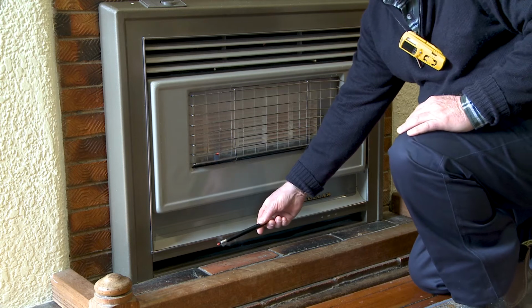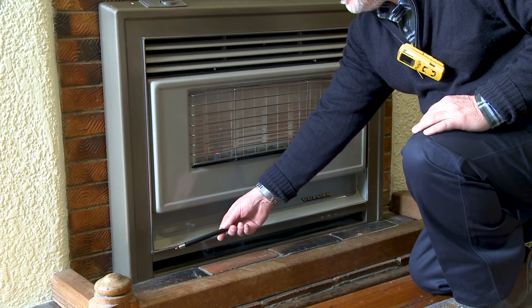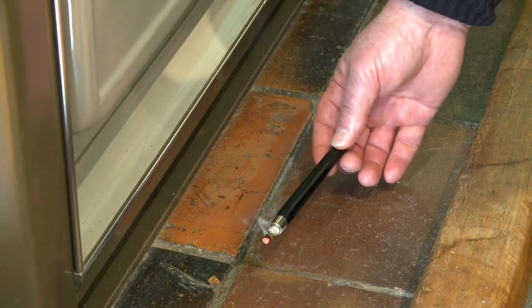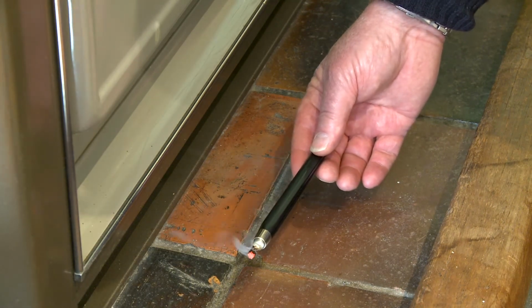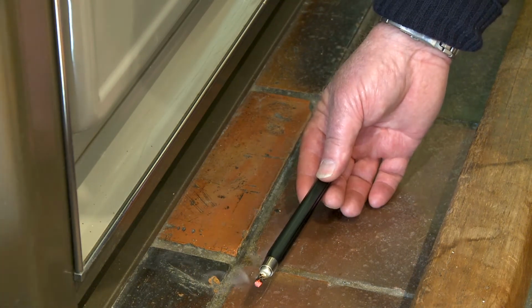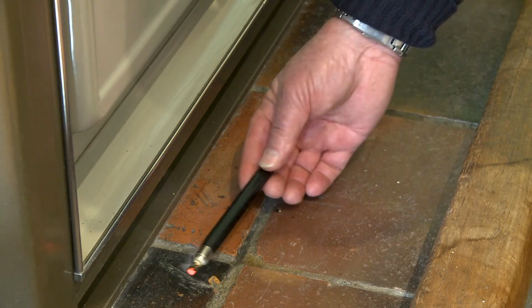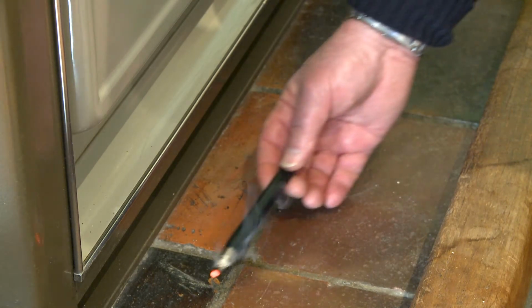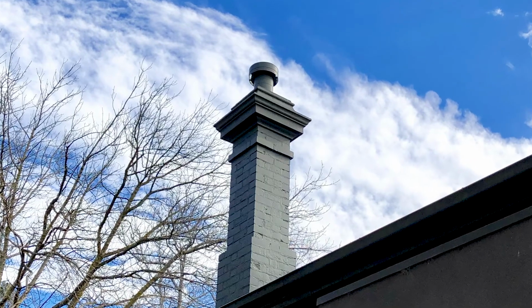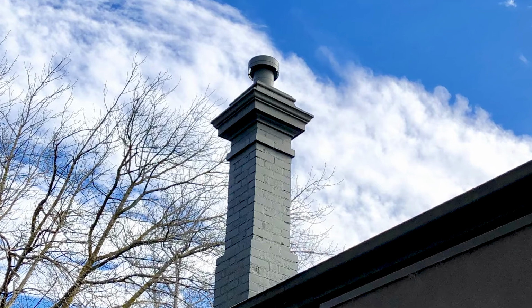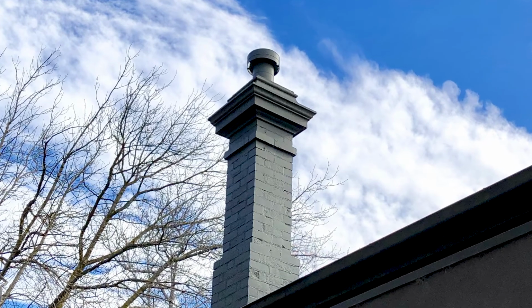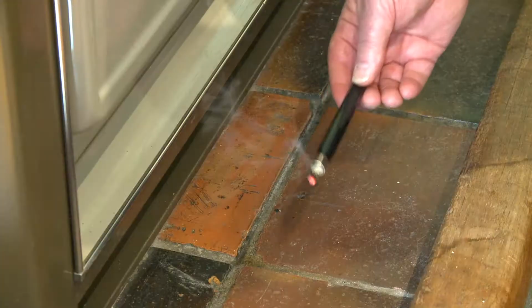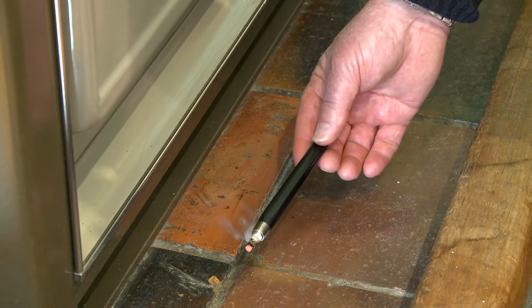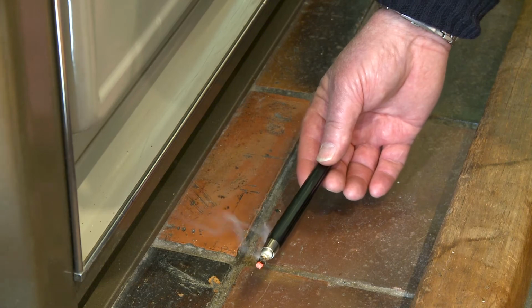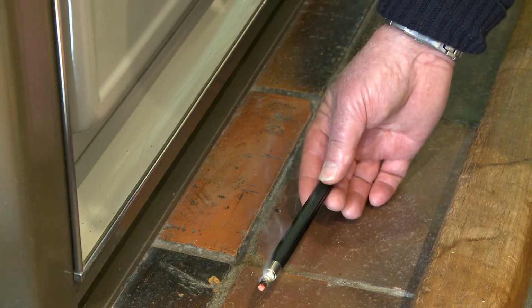Position a suitable smoke-producing device at the appliance draft diverter relief openings or next to any appliance openings for combustion air intake. Generate smoke and watch the smoke plume for any effect from weather conditions, for example, wind gusts or airflow within the flue or chimney due to temperature differences between the indoors and outdoors. Note any observable effect so that a comparison can be made when the test for negative pressure is conducted.